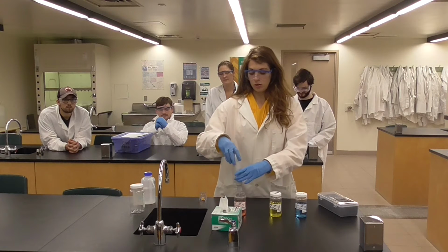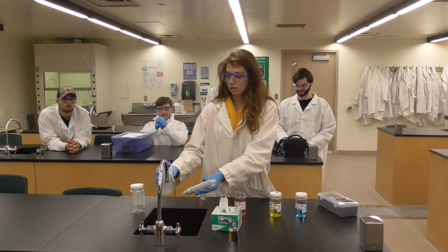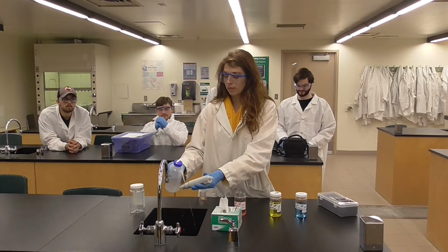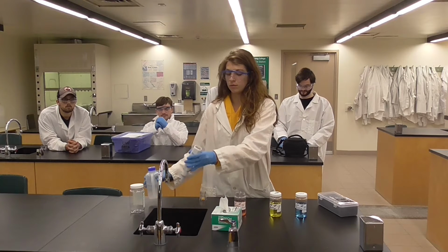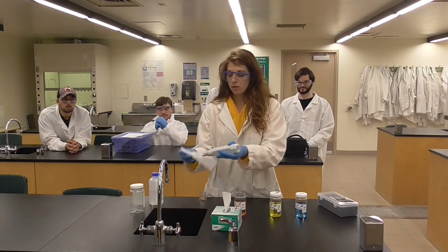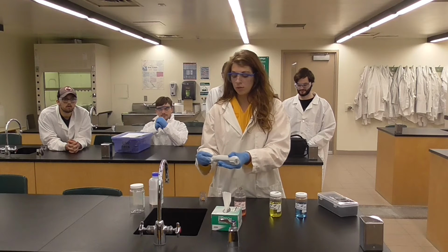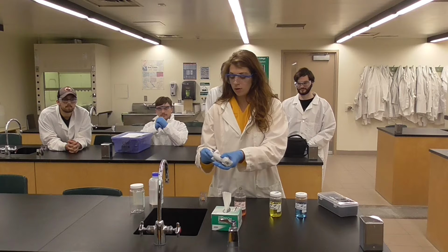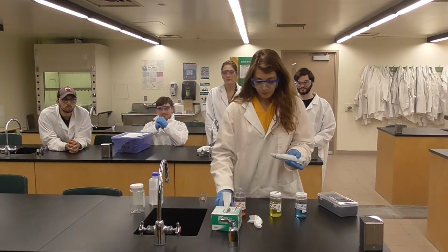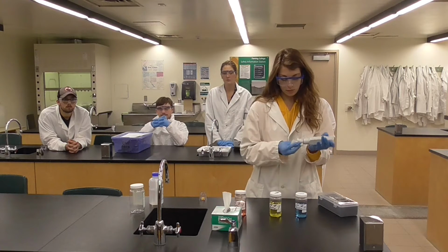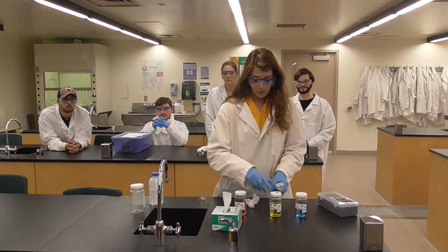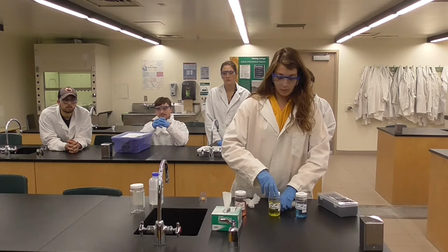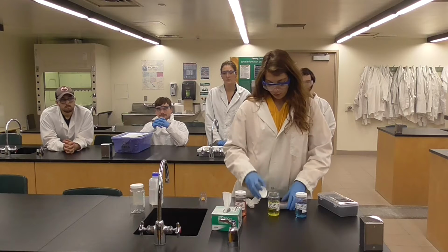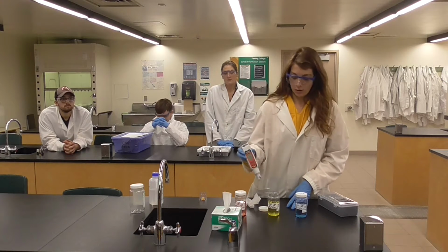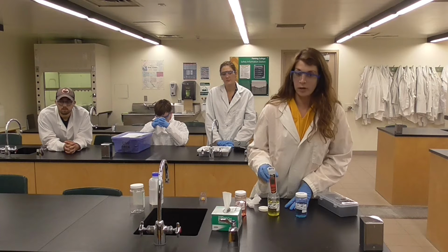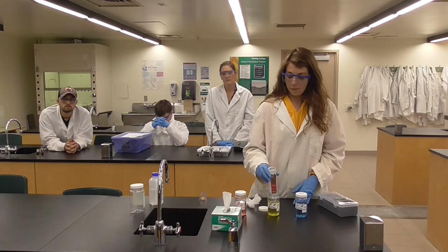To take it out and wash it in between instruments, you're going to rinse it with distilled water and dry it off with a Kim wipe to make sure there's no cross-contamination. This is the process of calibrating the machine before we start actually using the pH meter in another solution. Next, we use number 7. Again, it is starting again with putting it in and waiting for it to settle before we start calibrating the number.